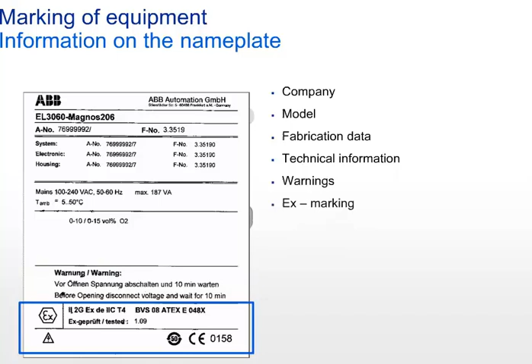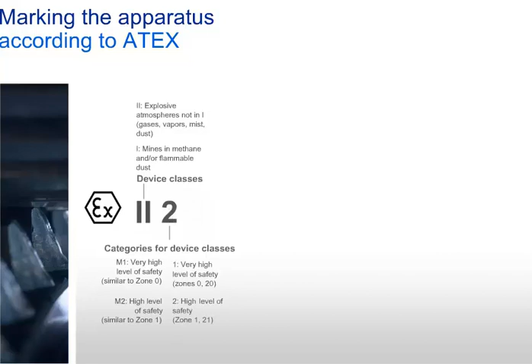Let's examine in detail what the Ex marking tells us. The Ex symbol is the marking for explosion prevention. Device class 1 or 2, which was described above. Depending on the level of protection, equipment categories are defined for Group 1 or 2. For device class 1, the categories M1 for permanent hazard and M2 for periodic hazard are defined. And for device class 2, 3 device categories are defined according to the ATEX zones.